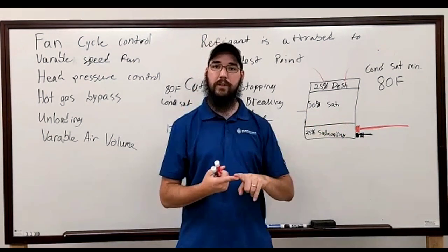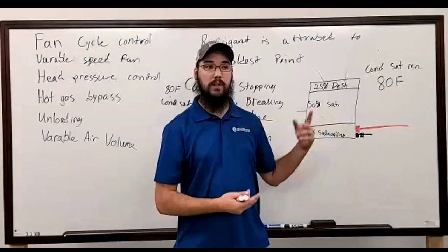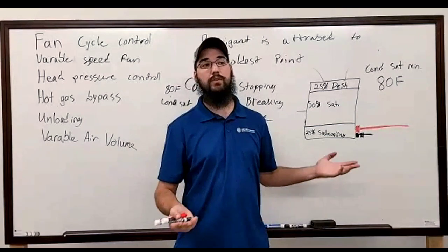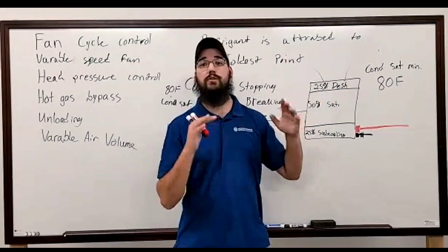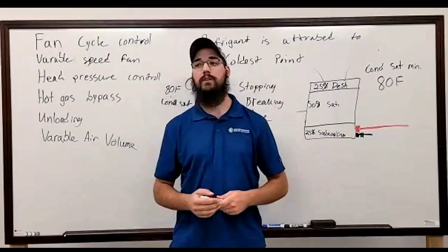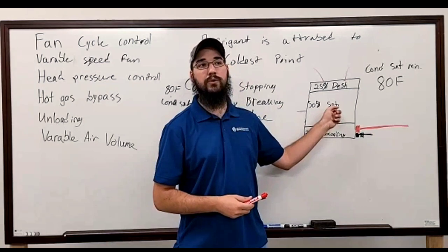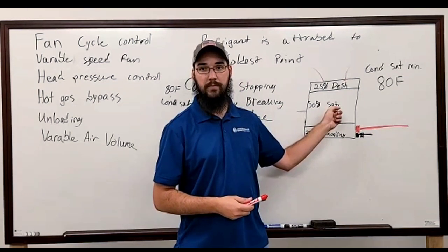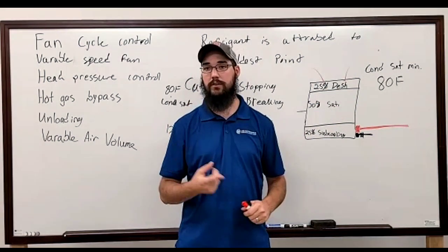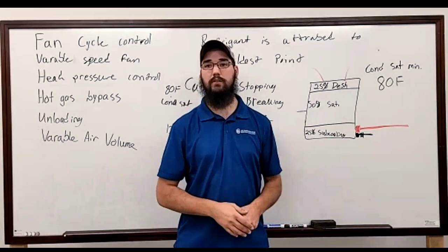And your coil is going to constantly freeze, and depending on which package they bought, likely will constantly be going into a defrost nonstop. If it ever goes into defrost, you know, if it's not just strictly going off of time. Some of them base it off of time, some of them base it off of coil temp. Most of the time on these that I've worked on, they're usually basing off of time. And in that amount of time, with no fan ever, one, they don't heat well because you're not picking up heat. And then two, they turn into this massive block of ice.